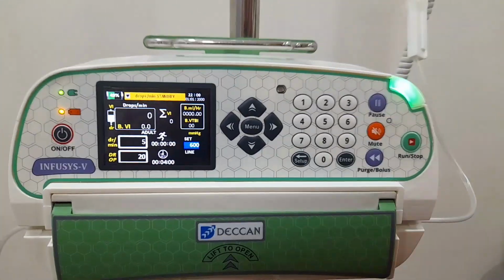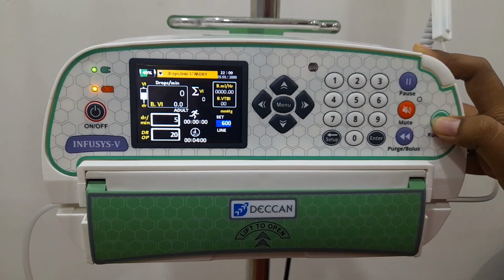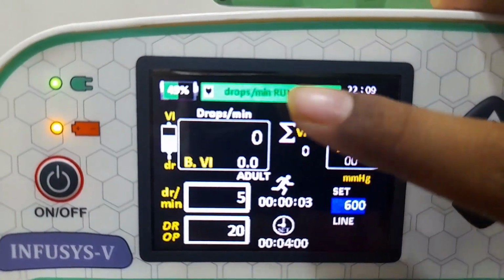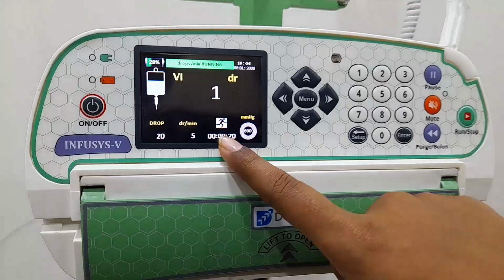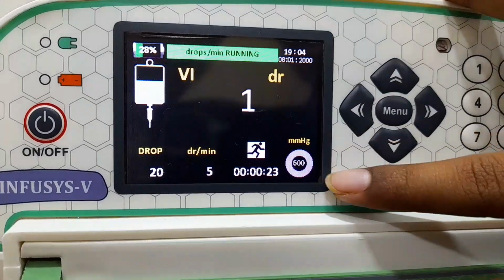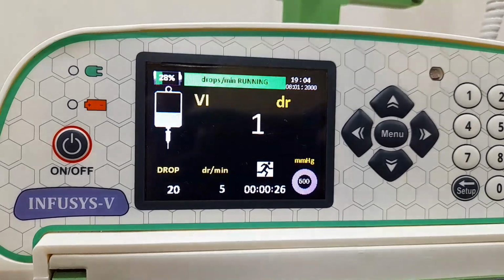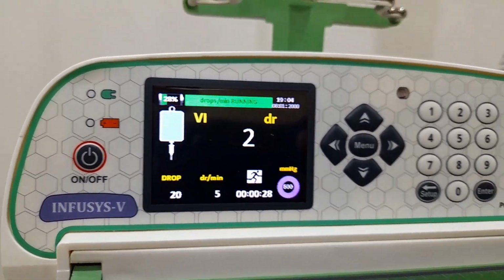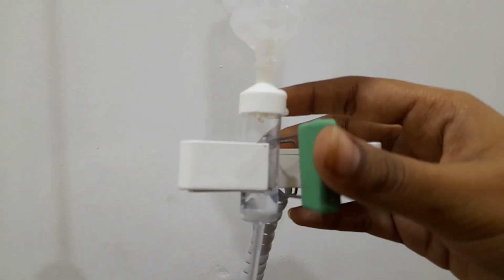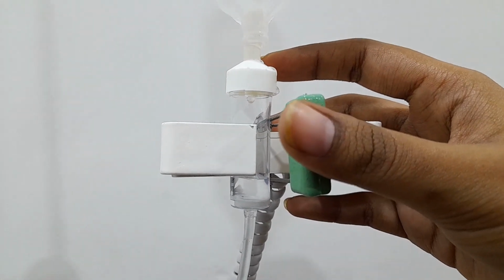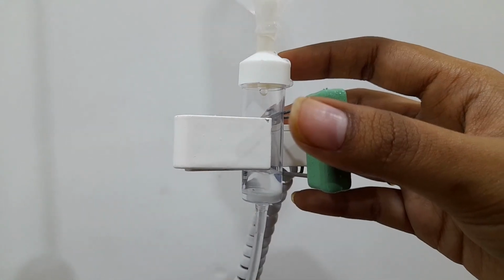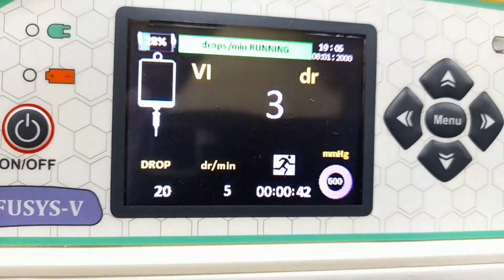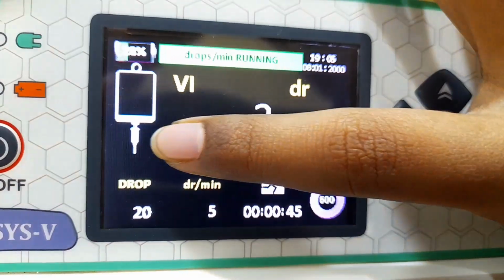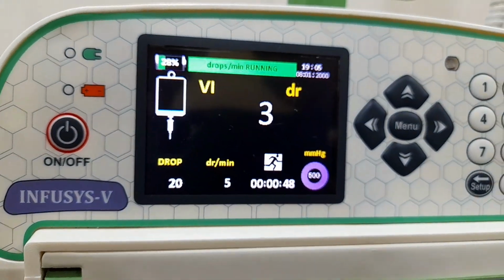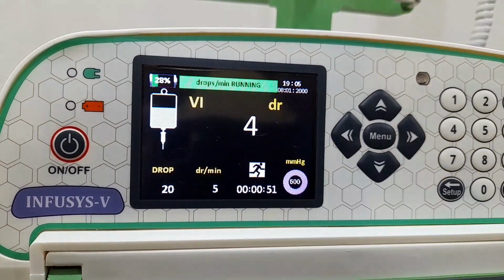Now we can start the infusion using the run/stop key. We started the infusion, and the drops per minute running status is updated in the status bar. After a 10 second delay, it automatically switches to the innovative multi-layer screen with various parameters like status bar, real-time date, month, year, battery backup percentage, infusion progress status, volume infused, occlusion set and inline graph, elapsed time, set drops and set drops per minute. Based on the drop sensor module and progress bar, we can see the changes in the VI. Now it changes to 4 drops.